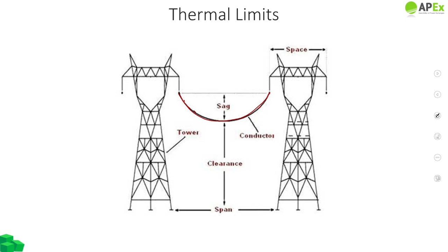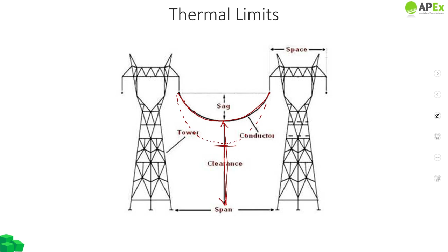What would happen here now is that the ground clearance, which was previously, let's say, slightly higher, would decrease to this point, right? And this decreased clearance from the ground could make it happen that it might come in contact with a tree or another object, causing it to fault. So this is also an issue that is caused once, let's say, more power is made to flow through the conductor beyond its thermal limit.